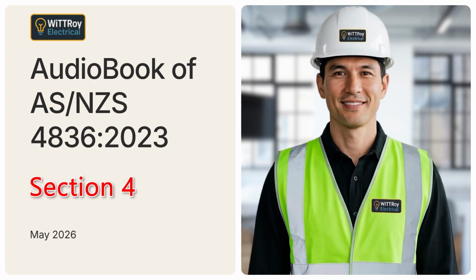Clause 4.3.14. Removing out-of-service electrical equipment and cables. Clause 4.3.14 explains the removal of out-of-service or decommissioned electrical equipment and cables. Before removal, the electrical equipment and cables must be isolated from all sources of supply. Tests must also be made to confirm that the equipment and cables are de-energized.